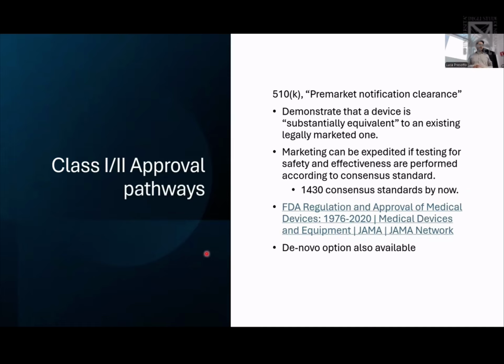And in most cases, what they work with is the pre-market notification clearance, 510K. The Americans like to use this kind of codes. And you need to demonstrate that the device is substantially equivalent, that's the legal term, to an existing one that's already legally on the market. And the marketing can be very expedited if the testing of safety and effectiveness is performed according to the consensus standards. The issue is that the last time that I updated these slides, there were 1,500 consensus standards. And if you want, there's an interesting historical overview of how the approval of devices went from when the legislation was invented in 1976 until 2020. But there are also some de novo options.